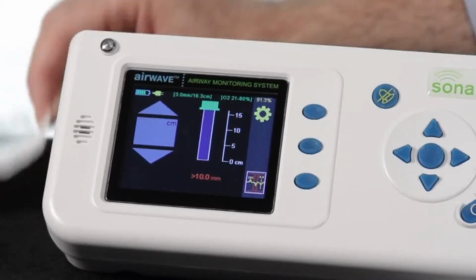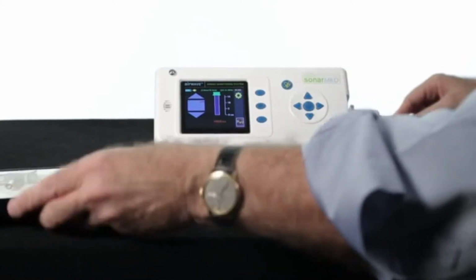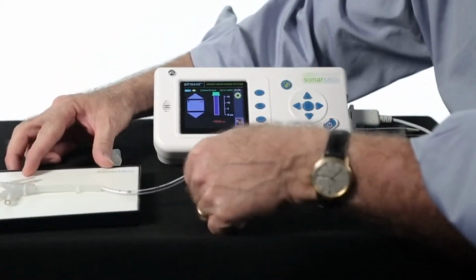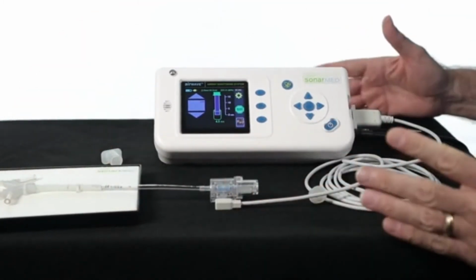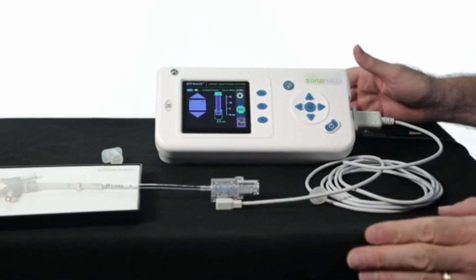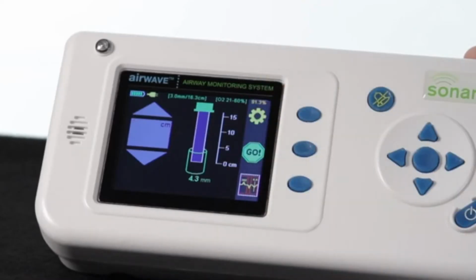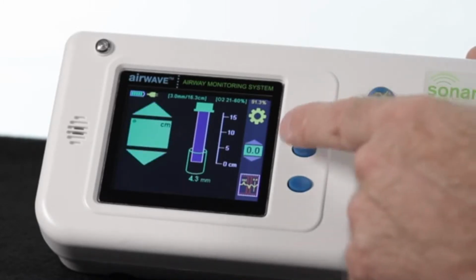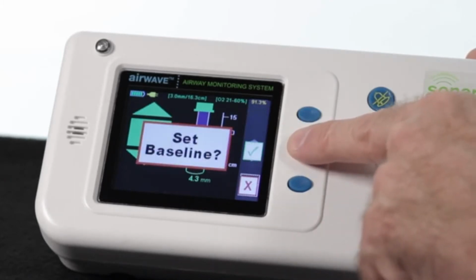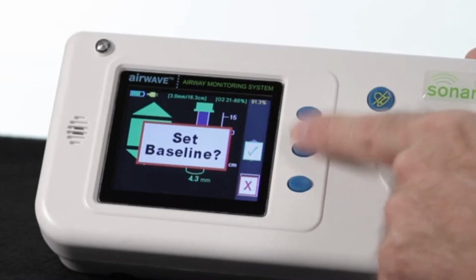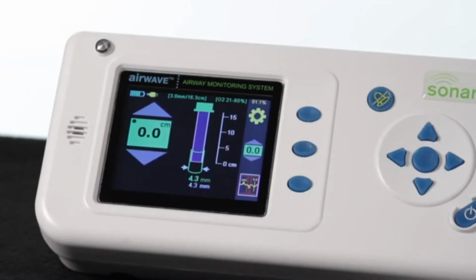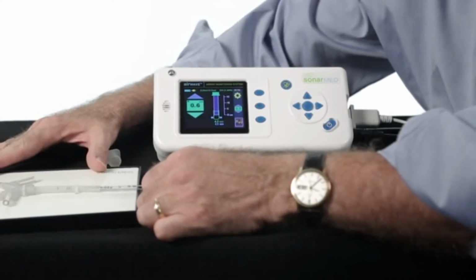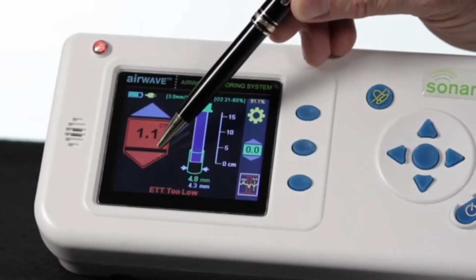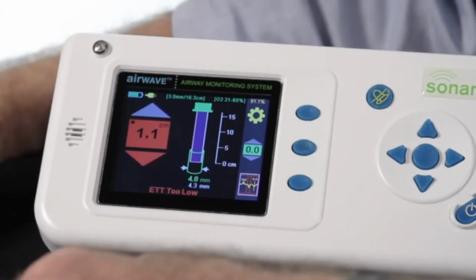Now we're ready to go ahead and intubate the patient. In setting the baseline, which is the next step, we want to basically measure movement of the endotrach tube from wherever it is at the point in time we set the baseline. So I've gone ahead and intubated into a fake trachea now, and there's a green go sign that's indicating to me, are you ready to go or start monitoring? I'll hit that go button. The flashing 00 means to set the baseline. I hit it 2 more times, once to get the set baseline sign up and then to confirm it. Now the monitor is ready to measure movement of the tube. So if the tube starts to move more proximally or move towards the carina, you'll see the downward arrow will light up, indicating that we've moved closer to the carina.